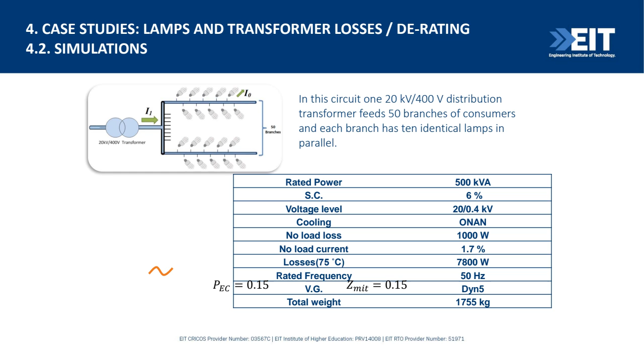In that simulation, the first harmonic for incandescent lamps was 0.9972 times the nominal current. For fluorescent lamps, it decreased to 0.9939 times the nominal current. For LED lamps, it decreased to 0.8457 times the nominal current, and CFL showed the worst case at 0.3 times the nominal current. So the maximum permissible transformer current with pure CFL lamps in our system is much lower than with incandescent lamps, and even much lower than with LEDs and fluorescent lamps.